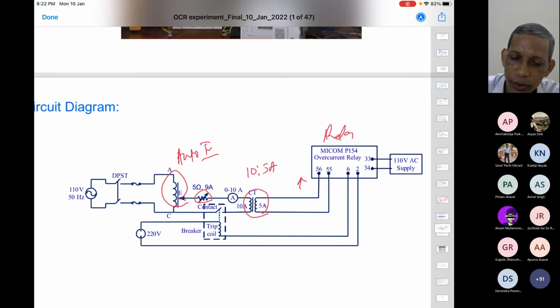And we inject current to this one. This is our experimental system. Earlier we were talking about theoretical things. This is a contact, this is a breaker here. This breaker can be controlled by this trip coil, which has a DC supply to energize this coil. And then from this end, the trip command comes here to open or break the corresponding circuit.